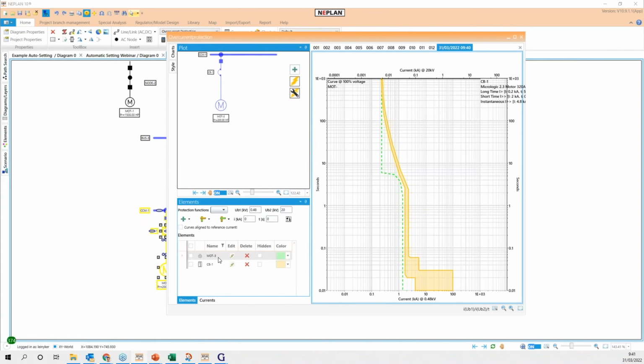So that means that, for example, we have the starting curve of the motor and we have the tripping time of the protection. So we can see, for example, what will happen in the scenario that the protection is not defined properly. In this scenario, this breaker will open the machine just if we are going to start the machine. So that is an improper setting of the protection. So graphically, NEPLAN allows to get the proper setting using the selectivity diagram.